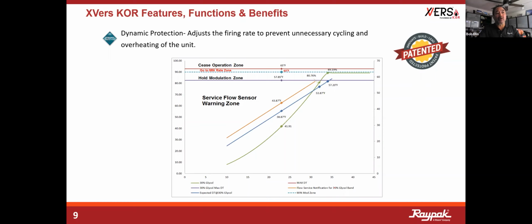But the other thing that is a part of that dynamic protection is, obviously, we're looking at delta T on those units as well. But there, in the way that unit operates, we're also taking into consideration glycol. Now, if you haven't compensated for the flow rate going through that unit for the glycol, that is the concentration in the water, you can program that in the commissioning process, and we'll take into account how much that reduces the heat transfer so that we don't overstress that heat exchanger.